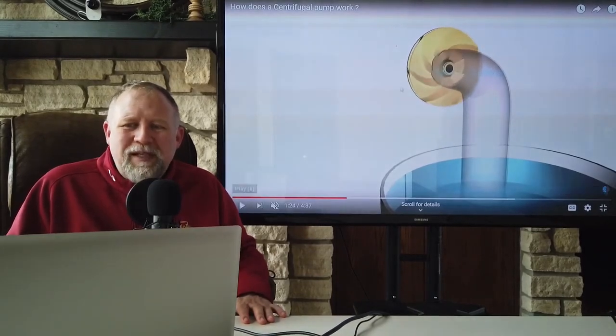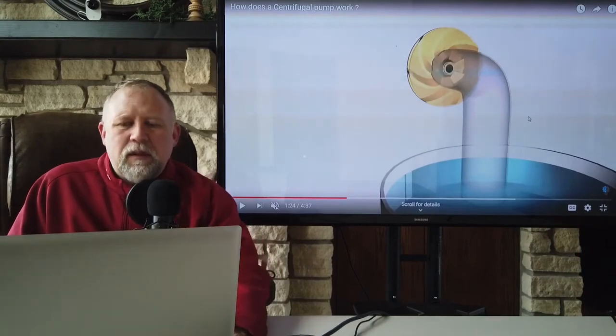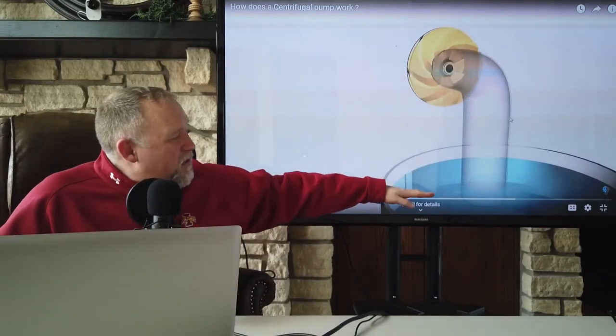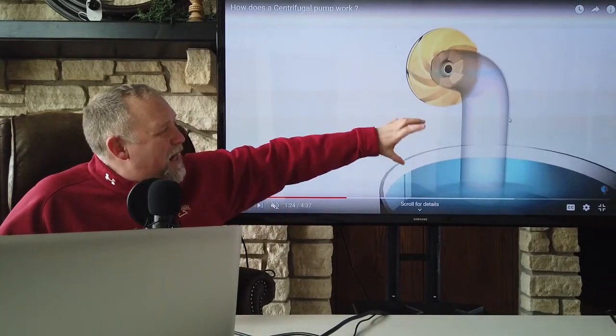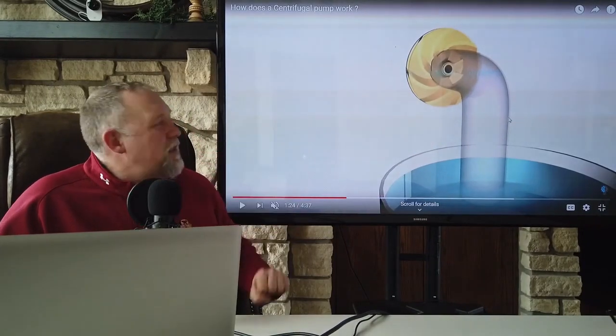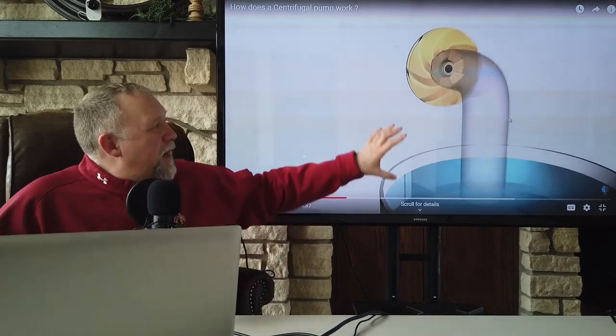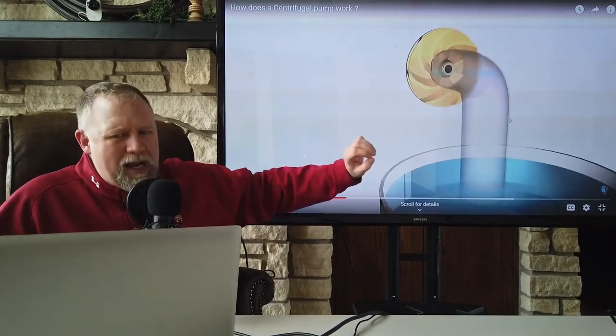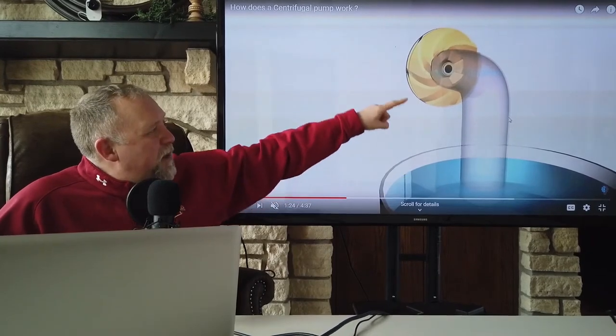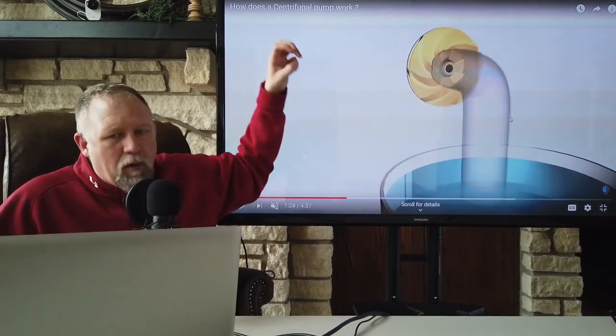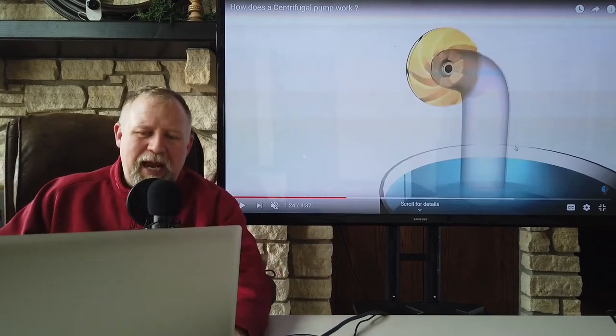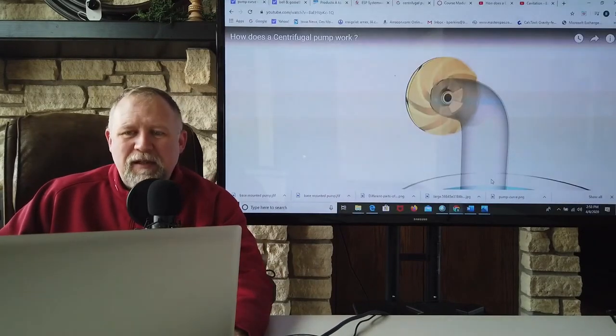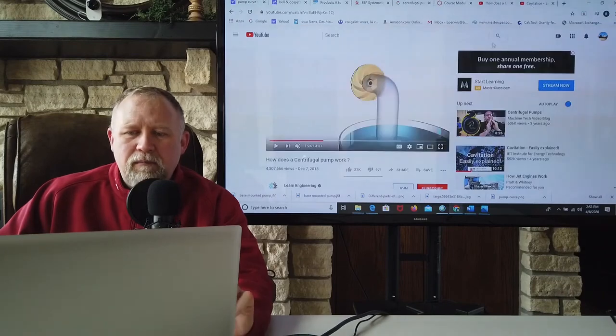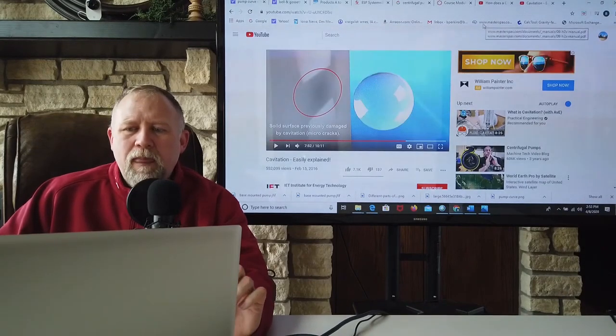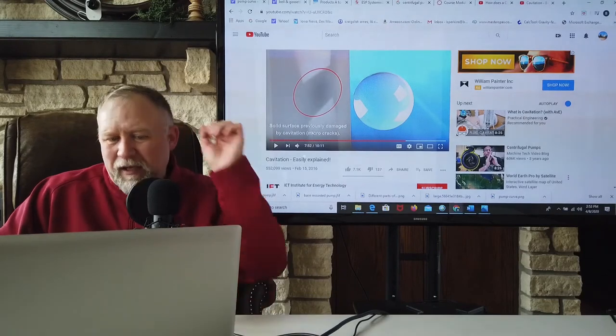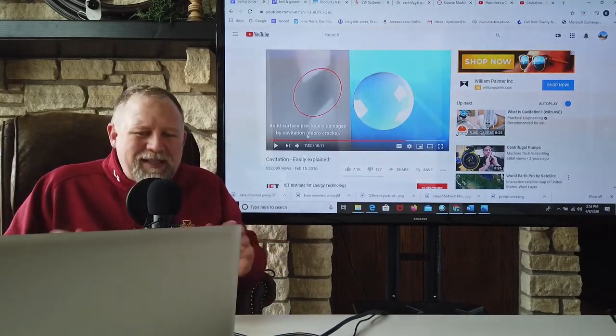All right, so what does cavitation look like? Oh, and this is also why there's limits to how far out of a tank an impeller can actually suck water into it. There's also a minimum amount of, a pump has to be primed. In other words, there already has to be water in this pipe for it to suck more water out of there. It can't just be sucking air. Now, some pumps are meant to be self-priming, but most centrifugal pumps for HVAC applications are probably not going to be self-priming.